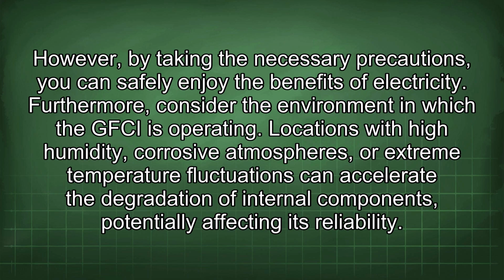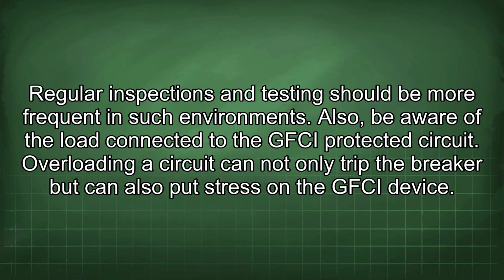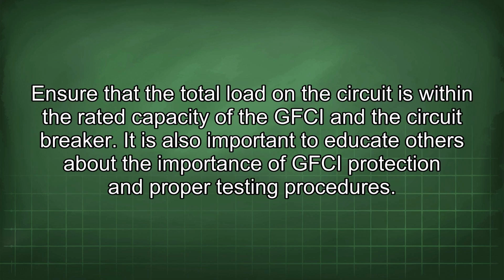Furthermore, consider the environment in which the GFCI is operating. Locations with high humidity, corrosive atmospheres, or extreme temperature fluctuations can accelerate the degradation of internal components, potentially affecting its reliability. Regular inspections and testing should be more frequent in such environments. Also, be aware of the load connected to the GFCI protected circuit. Overloading a circuit can not only trip the breaker but can also put stress on the GFCI device. Ensure that the total load on the circuit is within the rated capacity of the GFCI and the circuit breaker.